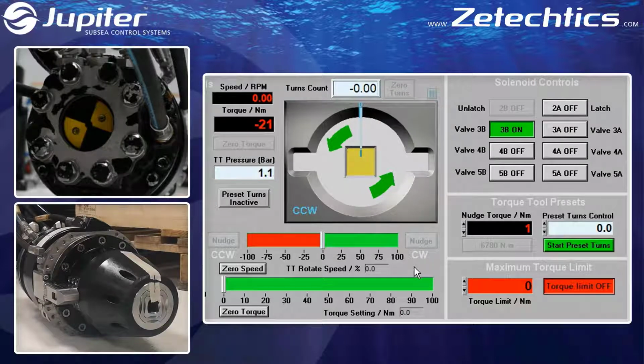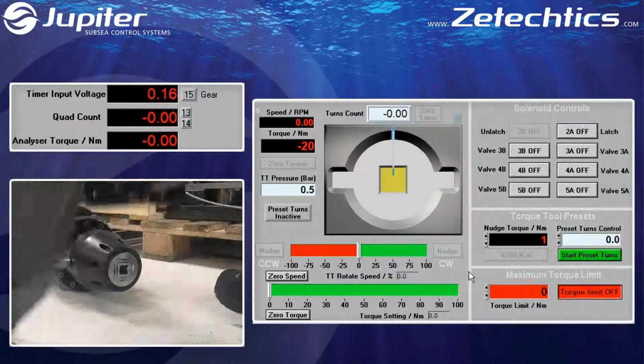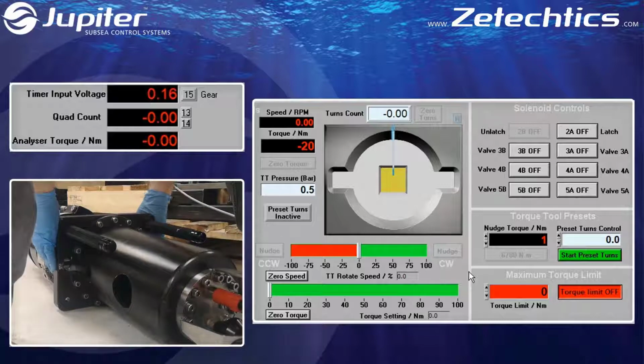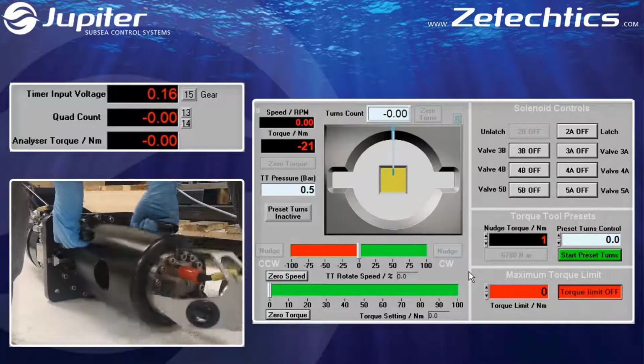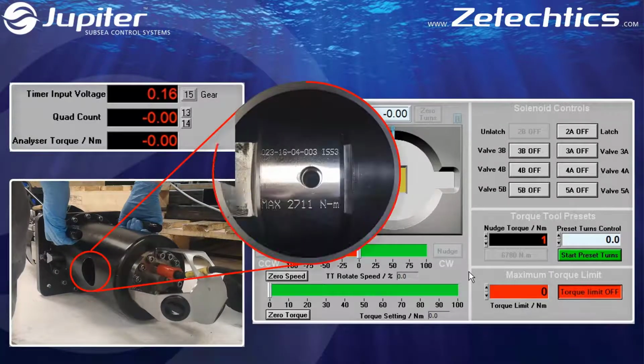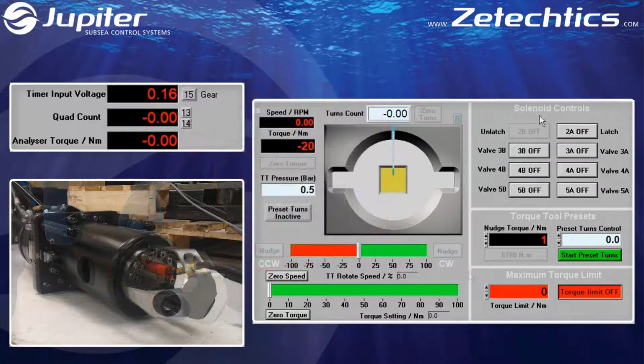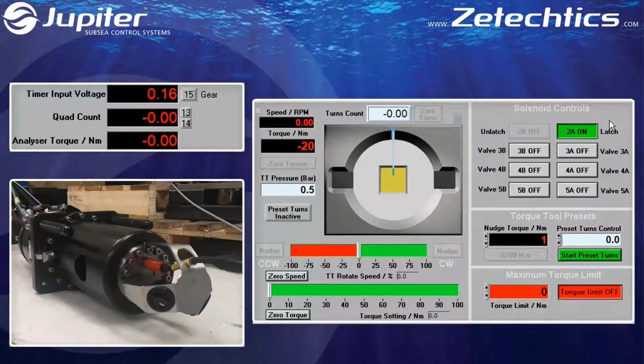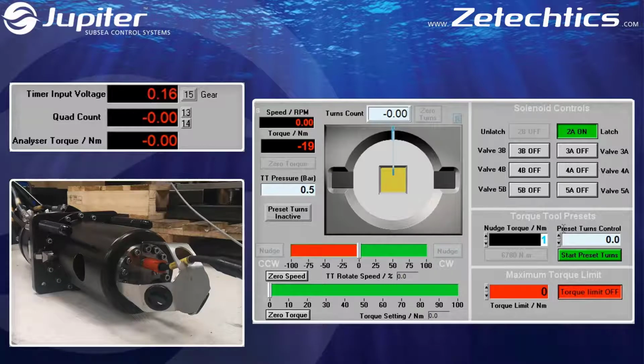The final step prior to calibration should be to test the torque feedback and preload the tool. Prior to fitting the torque analyzer bucket, ensure that the stem fitted is rated for the full range of torque to be applied, and that it has been zeroed. Fit the torque analyzer bucket to the tool, and operate the latches to ensure the bucket is secured. Set a nudge torque value that will provide 10 bar. If in doubt, operate the pressure valve again to find this.